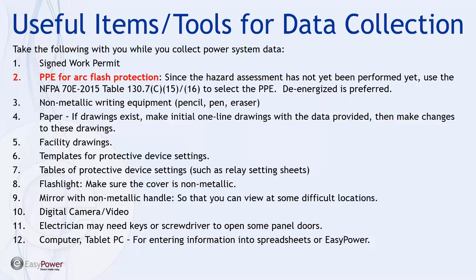Bring writing equipment including pencil, erasers, pens, paper, an initial one-line drawing, notes, facility drawings, and templates — specifically if you have adjustable protective devices where there can be multiple settings that have to be recorded. Even if you think nothing has changed in the plant, you want to validate that the data is correct and that the settings haven't been changed on any adjustable devices or fuses. Frequently, that can be a change that isn't documented, and that's the purpose of doing the data collection phase of the arc flash assessment.